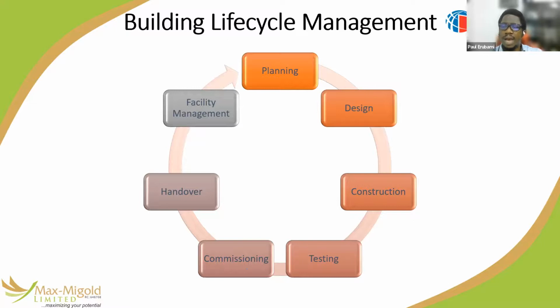That's what commissioning does. So in essence, when I want to do commissioning, I want to check that what was installed is adequate. I have an air conditioner in the training room, and it works well - you put your hand on it, it cools very well. But the training room is supposed to hold 40 people in class. If 40 people are in that class and the AC is cooling just as well, will they feel comfort cooling, or will they feel hot? If they feel hot, the AC might have tested positively in terms of testing, it passed testing, but it has failed commissioning. That training room is meant to hold 40 people actively learning - now they are not comfortable, even though the AC is cooling and chilling as much as it can. The body heat in the space is overwhelming that AC.